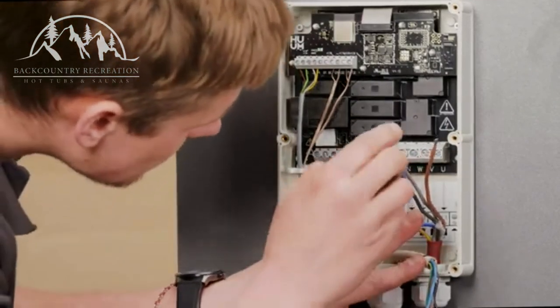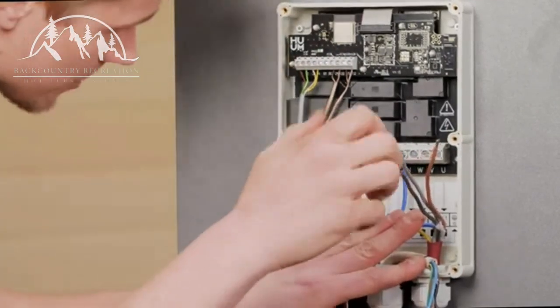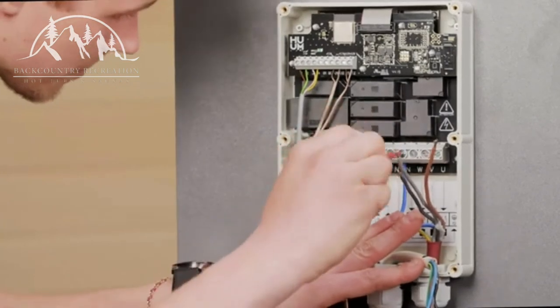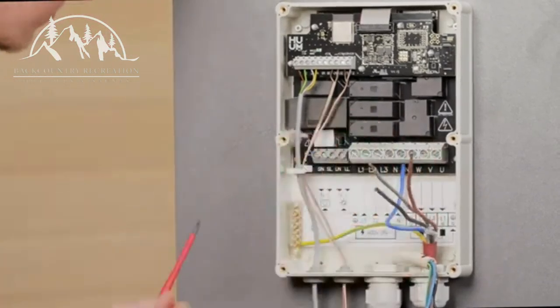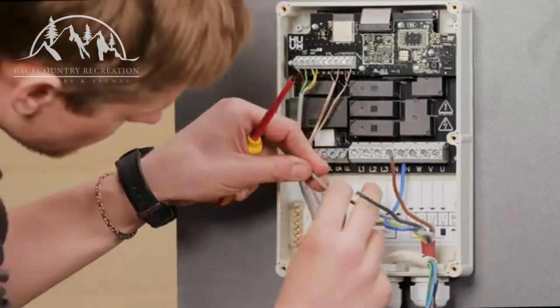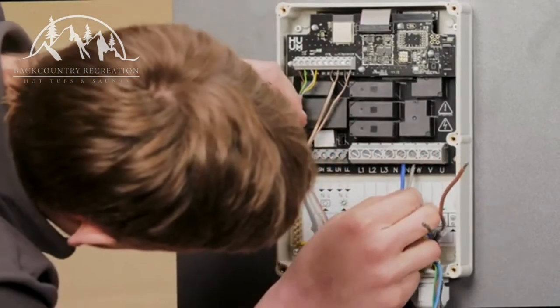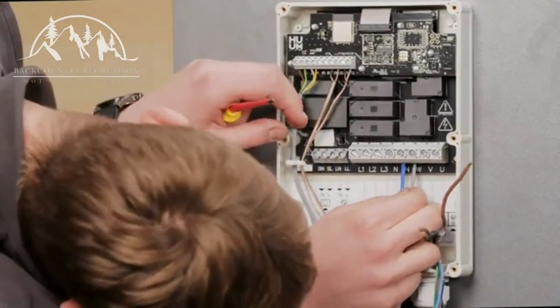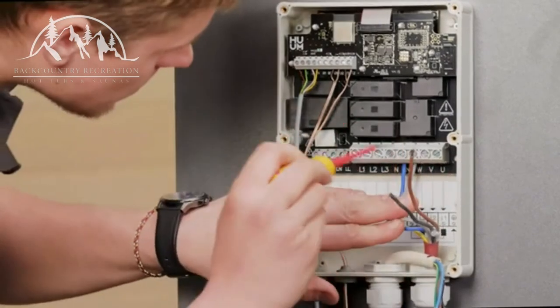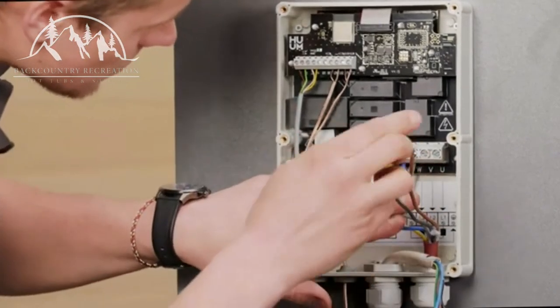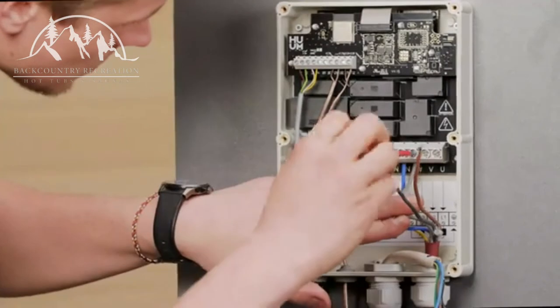Now the electrician can connect the power line to the heater. Don't forget, all cables to and from the main module need to have the same cross section. Then that power line needs to be connected to the main module. Once again, don't forget to save a picture after you've connected it. You'd never know when that information might be useful in future.